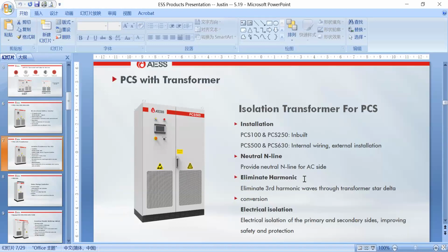Isolation transformer will provide us the neutral N-line. Okay, the second one, because of the harmonic. Please remember, there is an IGBT in our PCS, the inverter. So the IGBT will create the 3rd harmonic. We need our installation transformer to eliminate the harmonic for safety. Okay, the 3rd reason is electrical isolation. Okay, electrical isolation of the primary and the secondary sides, improving the safety and the protection.